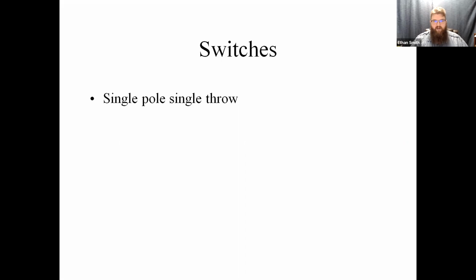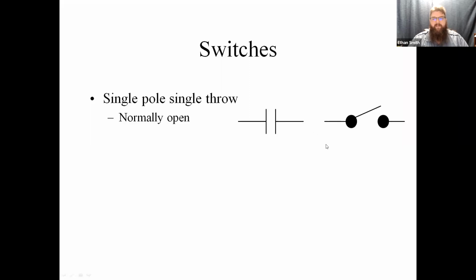So we have things called throws and things called poles. We'll start with the simple one. This is a single pole, single throw relay. So this would be a relay that has one armature. That's the number of poles that it has. And it has only an open or a closed position. So it's only got one set of contacts. So this would be a single pole, single throw switch. There are a couple of different ways that it can be pictured on your wiring diagrams. This becomes important later.